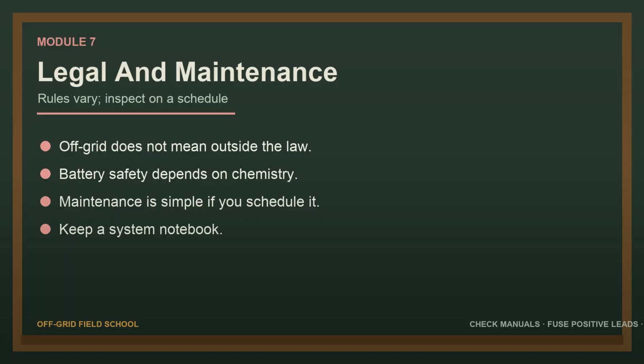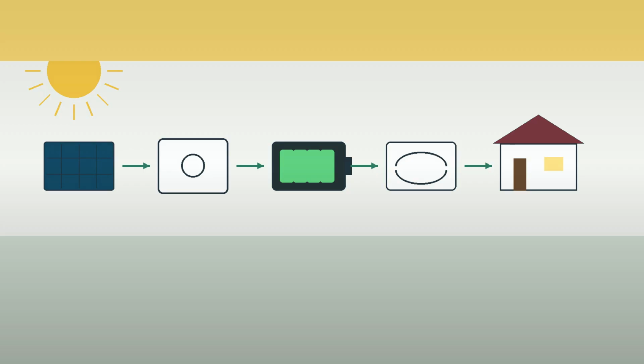12 volts is simple for tiny systems, vans, and low current loads. 24 volts is often cleaner once the inverter is larger or the cable runs grow. Higher voltage means lower current for the same wattage, which means less voltage drop and more manageable wire. Beginners can still build 24 volts, but they must match every controller, inverter, battery, fuse, and charger to that system voltage.